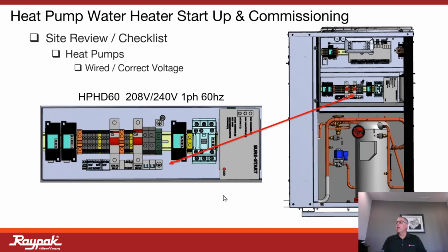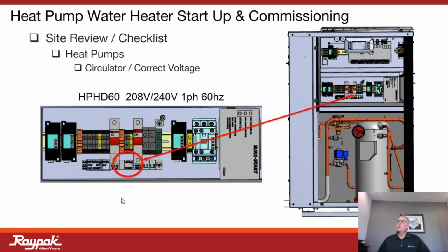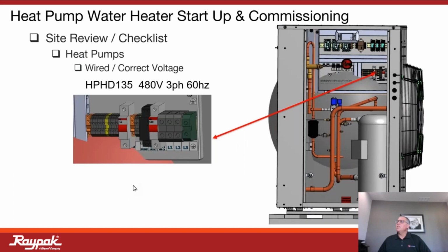So on our startup and commissioning, if we go through this as a punch list, things that we're going to be looking for, there's the close-up view of the panel, if you will, where we're bringing our primary power in. So the smaller units are 208 or 240 volt single phase, as displayed here. And then we'll go right to the circulator for that same unit. That terminal block is right there. These are essentially dry contacts so that we're switching power through these contactors. Again, we can switch whatever power we want through there. On the larger units, that is 480 volt three phase, so that wiring will necessarily look a little bit different. Making some notes here.